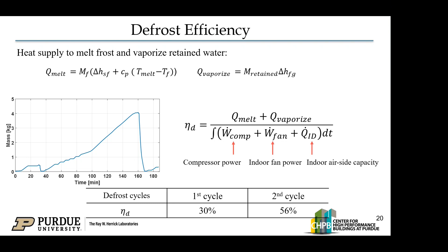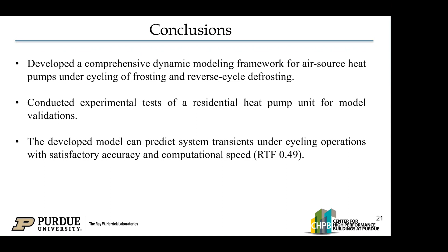The conclusion is that we developed and experimentally validated a dynamic modeling framework for an air source heat pump and the cycling operation of frosting and defrosting. And for this system, the simulation speed, the real-time factor, is close to 0.5, which means the model can run 2 times faster than real time. It is okay for simulation, but for control and fault detection applications, it's still challenging. So more work could be done on the simulation speed.